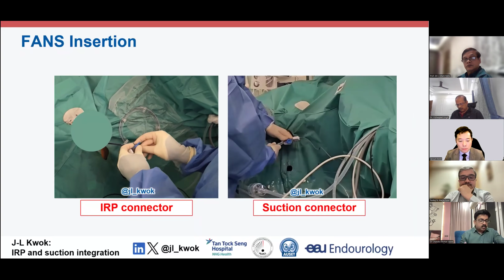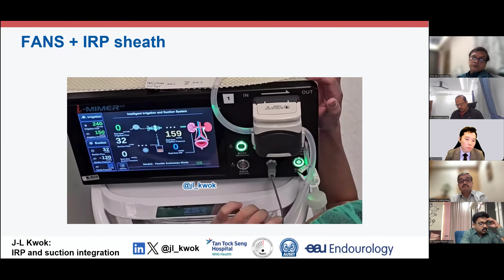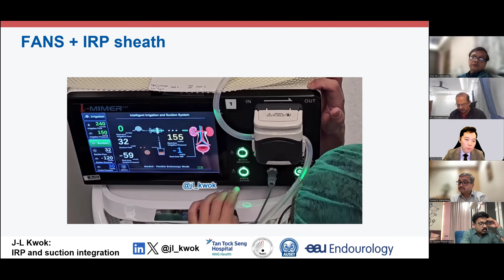And subsequently, you attach the IRP monitor to the machine and it starts at 0, and then you put in your irrigation pressure as well as the suction pressure, and you see what you like. This is a very precise touchscreen where you can put in exactly the values you want. Irrigation and then suction is on, and it's real-time monitoring, calibrating your inflow pressure as well as the suction pressure to not go beyond the 30 mmHg that you've set.